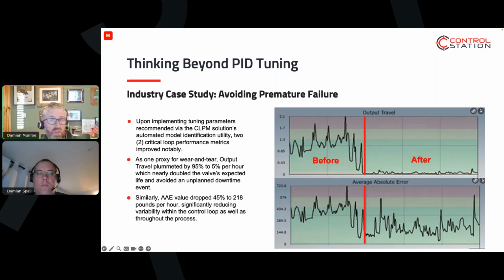Understanding why that process has changed will then focus you in - the output travel is high because the oscillation has gone high, and it shows you that, actually, we added a new product here. We're running a different recipe, where in this case they had increased the flow rate through the process, which caused variation in the model fit, which then required a tuning change to adjust the parameters to suit it.